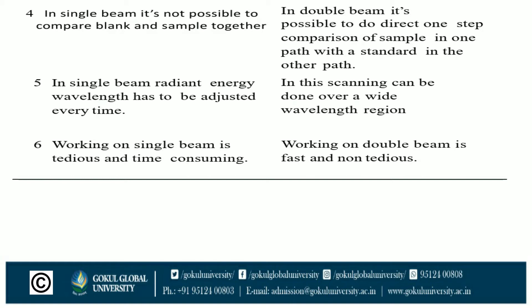Fifth: in the single beam, the radiant energy wavelength has to be adjusted every time. In the double beam, scanning can be done over a wide wavelength region. Sixth: working on the single beam is tedious and time-consuming, whereas working on the double beam is fast and non-tedious.